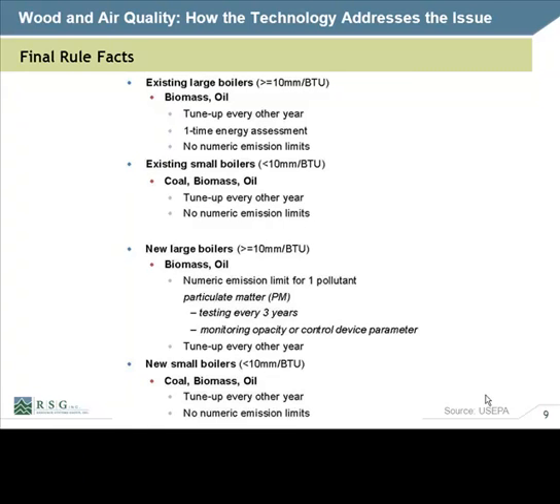It's also divided into large boilers and small boilers. Large ones are greater than 10 million heat input, small boilers less than 10 million. If you're less than 10 million, you don't have an emission limit to meet. If you're greater than 10 million, you have an emission limit, and you need to start thinking more intently about emission control technology to meet federal requirements.